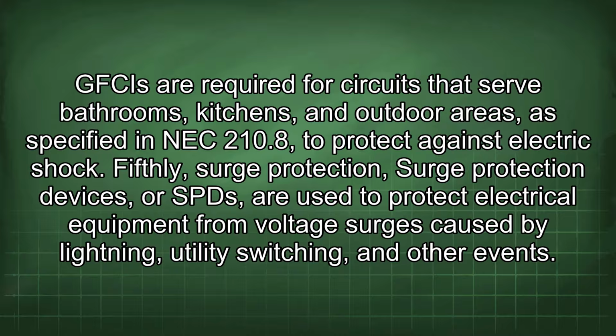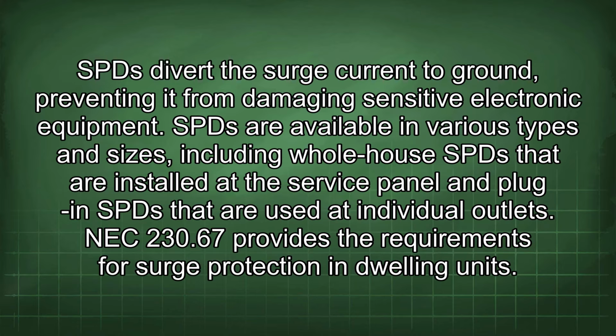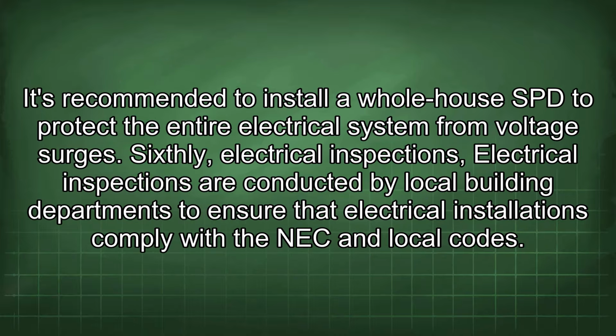Surge protection devices, or SPDs, are used to protect electrical equipment from voltage surges caused by lightning, utility switching, and other events. SPDs divert the surge current to ground, preventing it from damaging sensitive electronic equipment. SPDs are available in various types and sizes, including whole-house SPDs that are installed at the service panel and plug-in SPDs that are used at individual outlets. NEC 230.67 provides the requirements for surge protection in dwelling units. It's recommended to install a whole-house SPD to protect the entire electrical system from voltage surges.